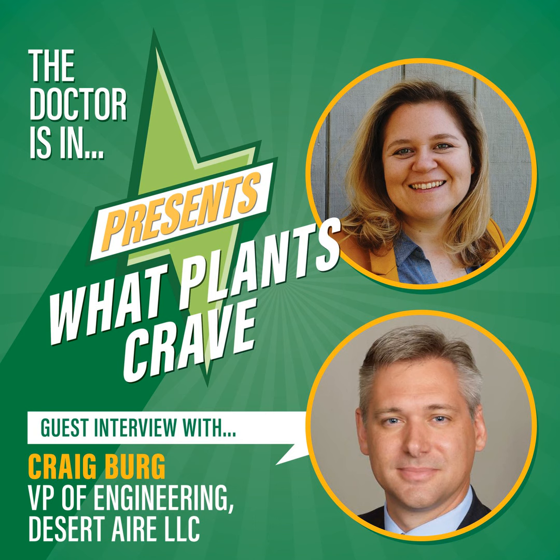Well, two reasons, potentially. Number one, if we're getting down to the point where we're going to freeze the water on the coil, let's say we've got a compressor that's too large for the airflow and everything else that we've got going on in the system, we can push a little hot gas in there and reduce the capacity of the evaporator coil so that it's a little bit warmer, and now we don't freeze on it. So it can be a freeze protection type of device. It can be a capacity control device where, okay, we don't want to do quite as much capacity. So we're going to have that a little bit warmer, right?